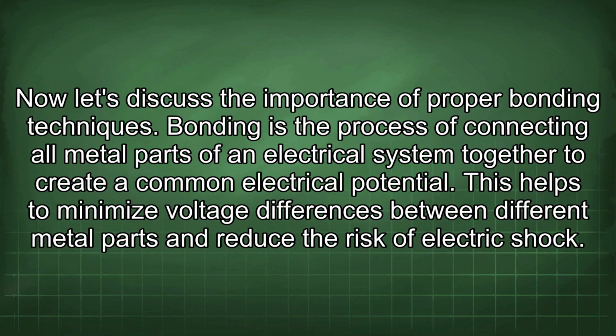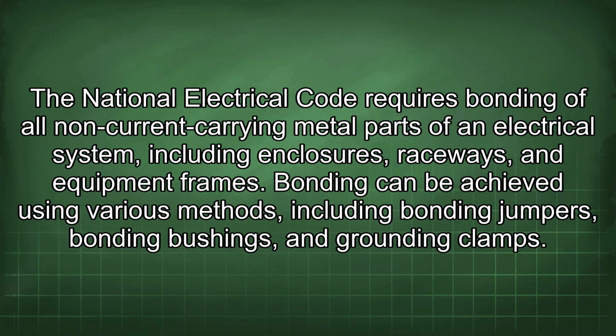Now let's discuss the importance of proper bonding techniques. Bonding is the process of connecting all metal parts of an electrical system together to create a common electrical potential. This helps to minimize voltage differences between different metal parts and reduce the risk of electric shock. The National Electrical Code requires bonding of all non-current carrying metal parts of an electrical system, including enclosures, raceways, and equipment frames. Bonding can be achieved using various methods, including bonding jumpers, bonding bushings, and grounding clamps.